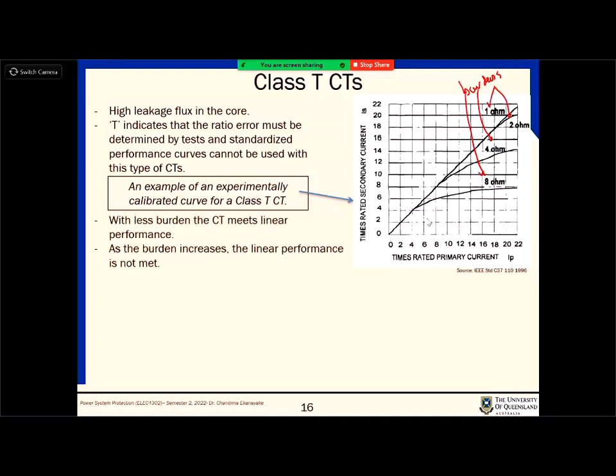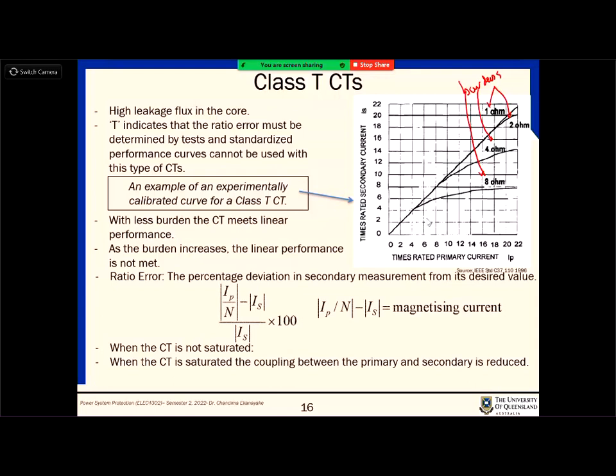With less burden, the CT meets linear performance. When the burden increases, the linear performance is not met. Again, you can mention how to find the error associated with this. When you connect different burdens, what is the error? Error is basically the primary current divided by the number of turns minus the secondary current, with respect to the secondary current, right?